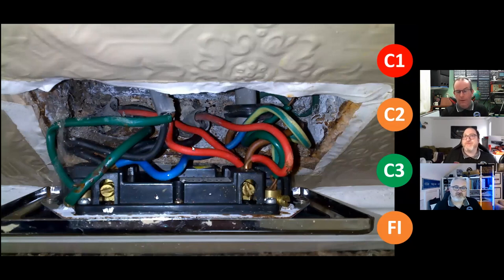So for me, straight away, I open that and I think, well, first of all, there's evidently damp in the wall because that box is corroding. There is definitely some. So the back box is corroding. I'm not seeing much mechanical protection on the cables as they enter the box. No. Somebody knew about grommets, but didn't really... So what's happened there? They put the grommet in, but then the cable's been put in afterwards, or it's pushed the grommet in as they've pulled it, or it's pulled it as they've pulled it.